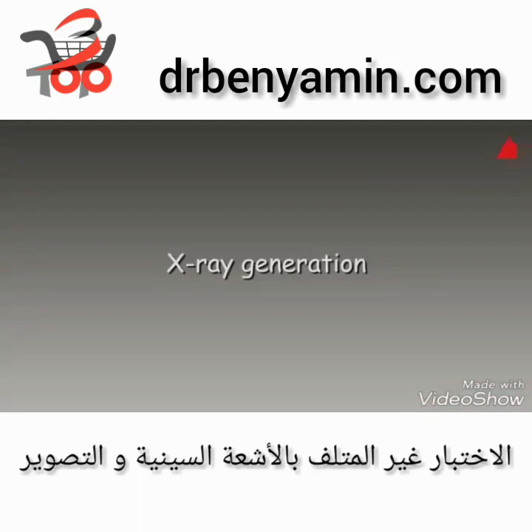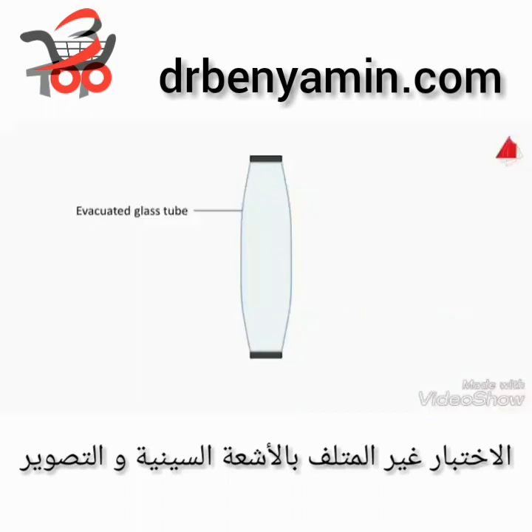But how are X-rays actually produced? They are generated in a so-called X-ray tube. To build an X-ray tube, first of all a thin-walled glass tube with a high vacuum within is needed. In the lower part of the tube, a V-shaped wire made of tungsten is positioned. This is the so-called thermionic cathode.